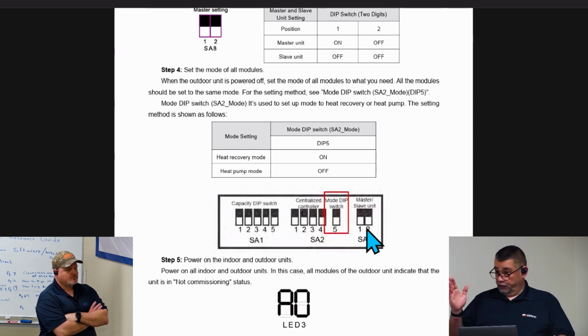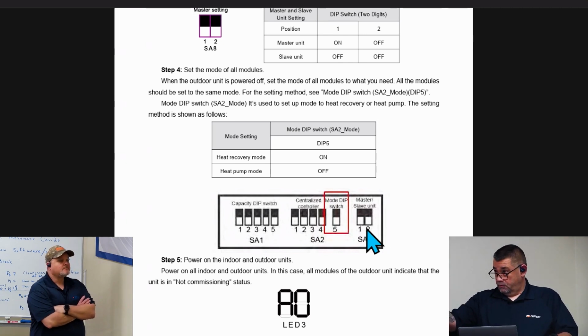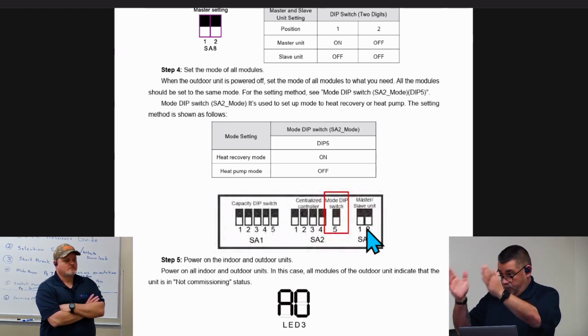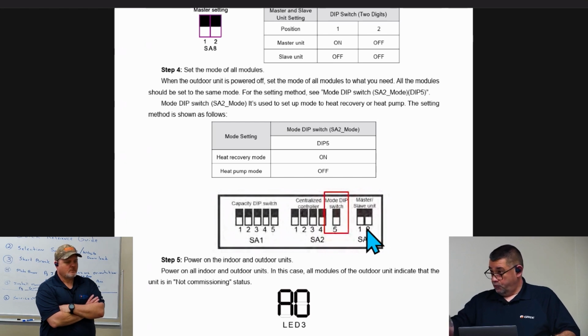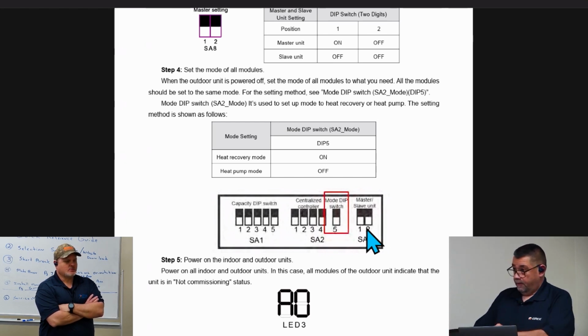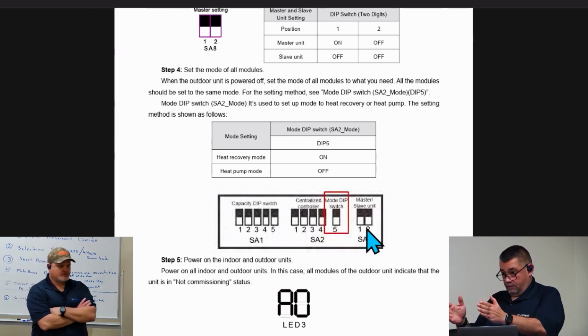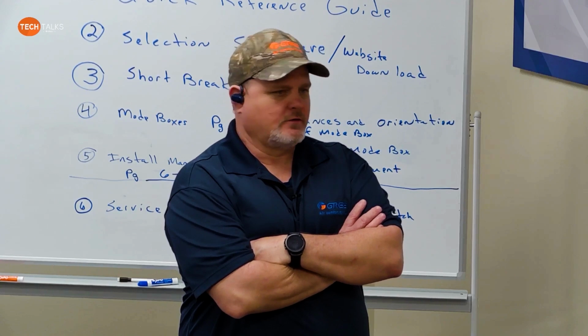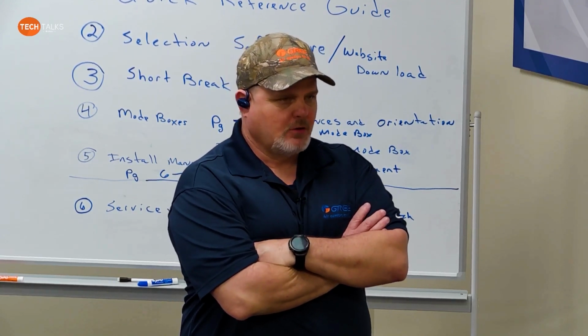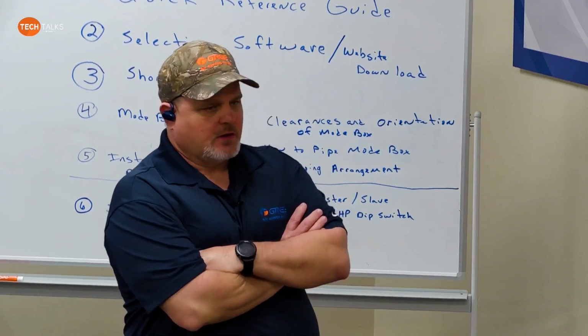Okay, so the first unit, and I believe you mentioned it, Greg, when you are looking at the unit installed on a rail or however it is, the closest unit to the piping to the building is what you normally set as your master. So it doesn't make a difference if in this particular configuration the 8-ton is here and the 6-ton is closest to the building? No, it doesn't matter if the 6 tons or the 8 tons is closest to the building. Whatever one's closest to your building piping, that's the one you make your master. If you have more than one system, follow that same arrangement to make it easier for you.